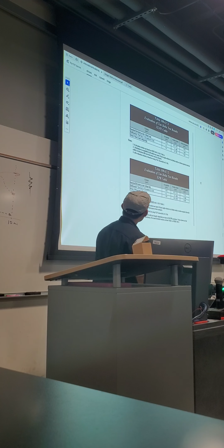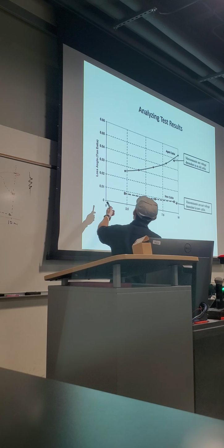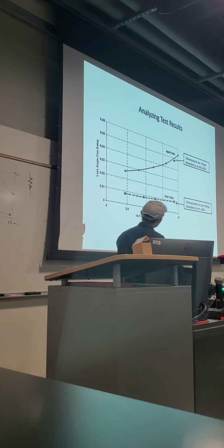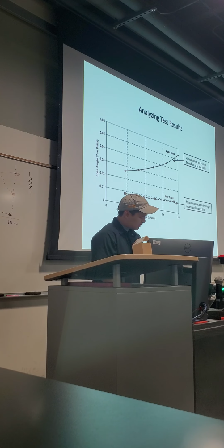These two extruded dielectric cables are going to have different evaluation criteria. So in this case, we're saying what is acceptable and what is not. If it's less than 0.1, and we'll look back at this example chart, definitely less than 0.01, then it's going to be acceptable.